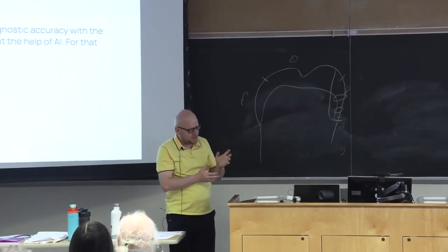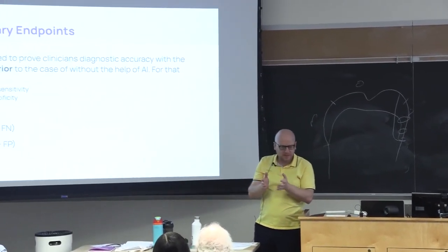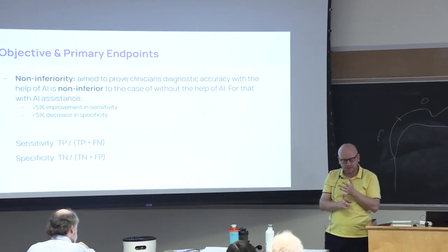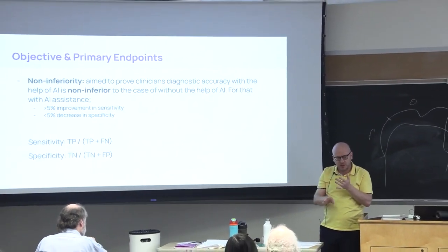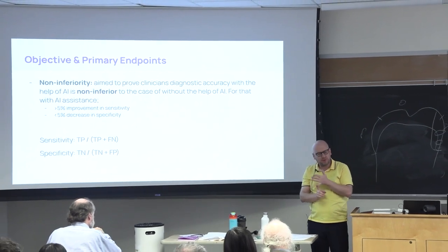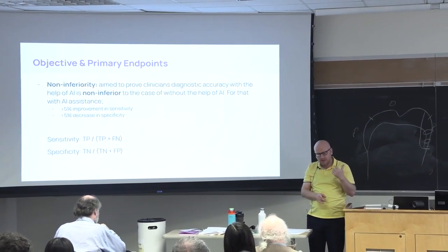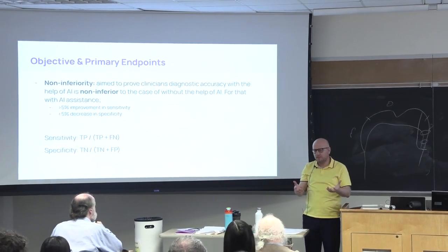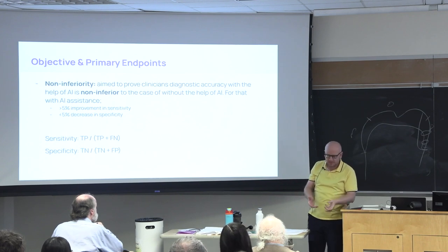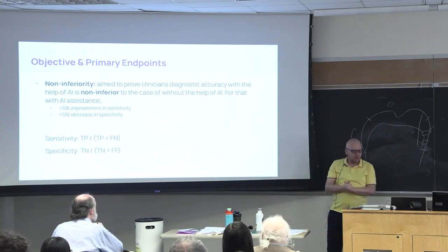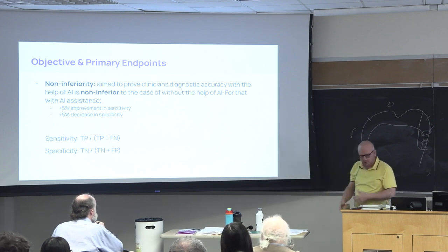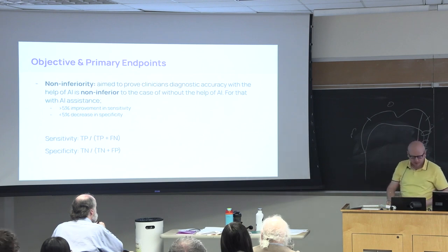So essentially that means we are being risk averse for the patient. FDA is being risk averse for the patient, and the risk for them is if there is a false positive, then that surface is gone. So we need to provide the metrics at the surface level. With surfaces, true negatives are limited, right? So it's not ill-defined now. You have 3 surfaces, total 32 teeth. In a mouth, at most, you will have 96 true negatives. So now we have solved the problem of the ill definition of true negative. With surface level metrics, again, we have already provided all the other metrics that are possible, that are not ill-defined, to FDA in an auxiliary statistical analysis.